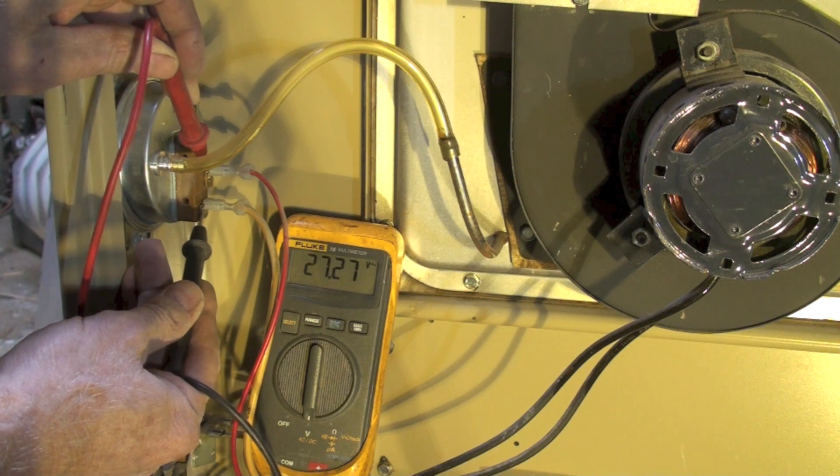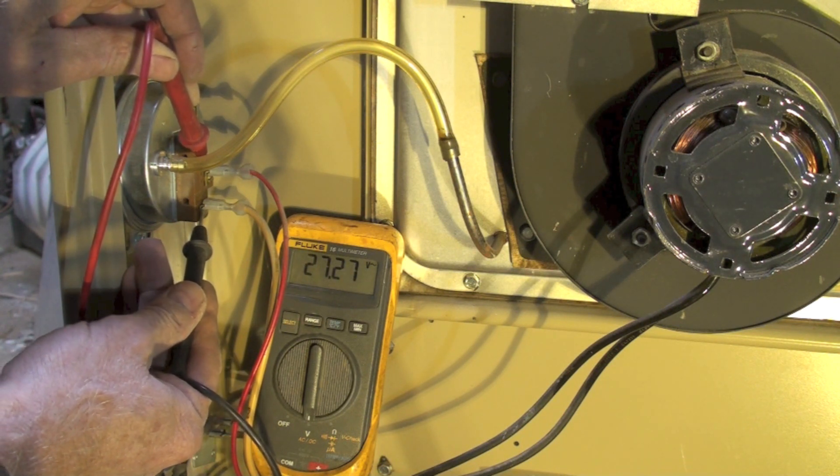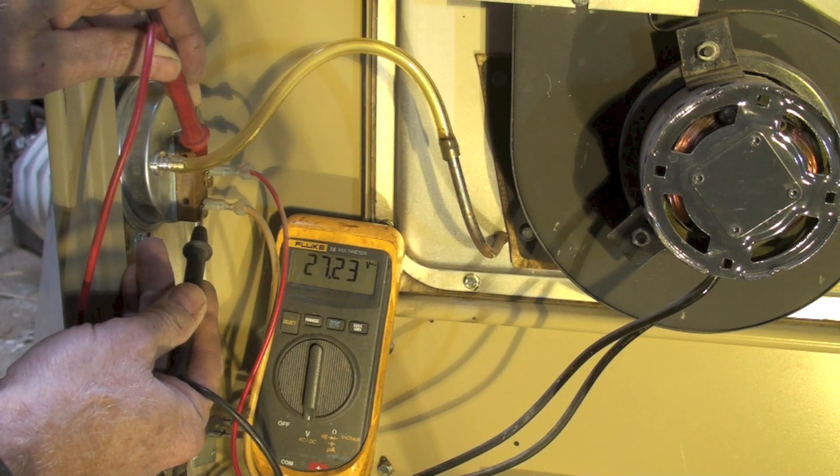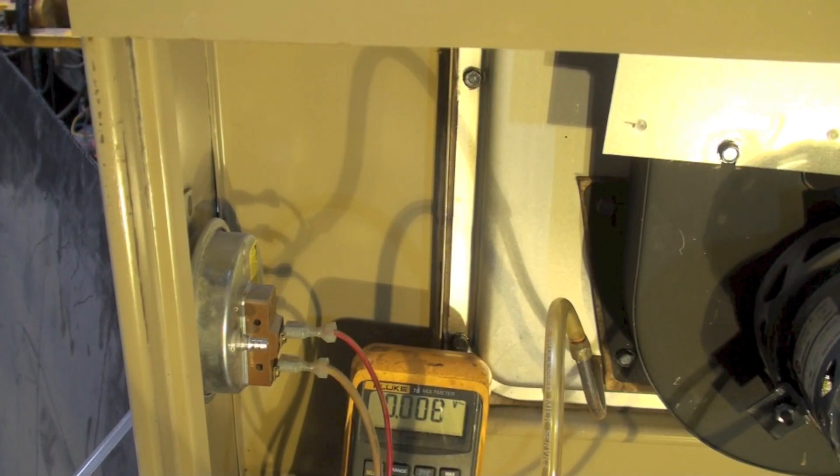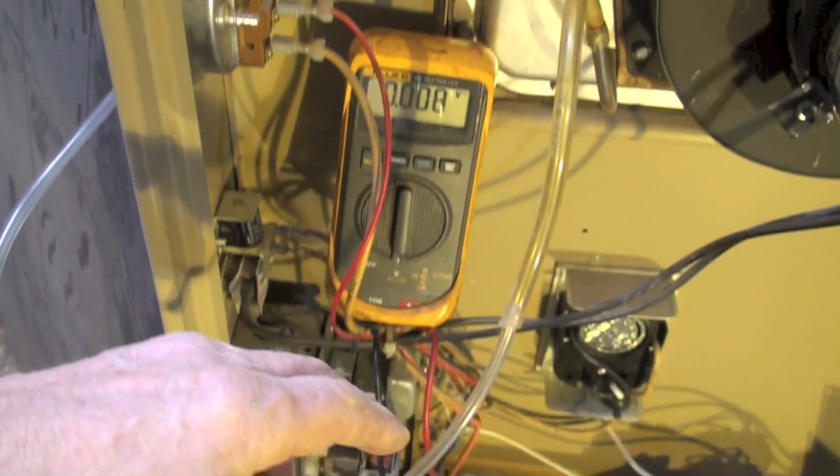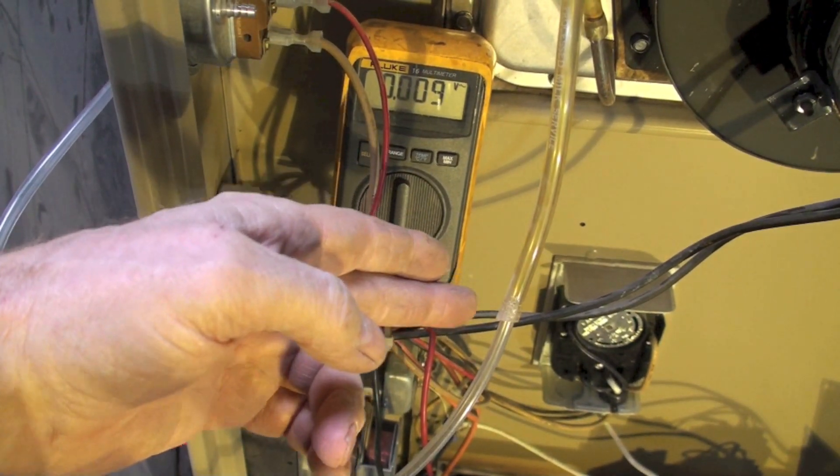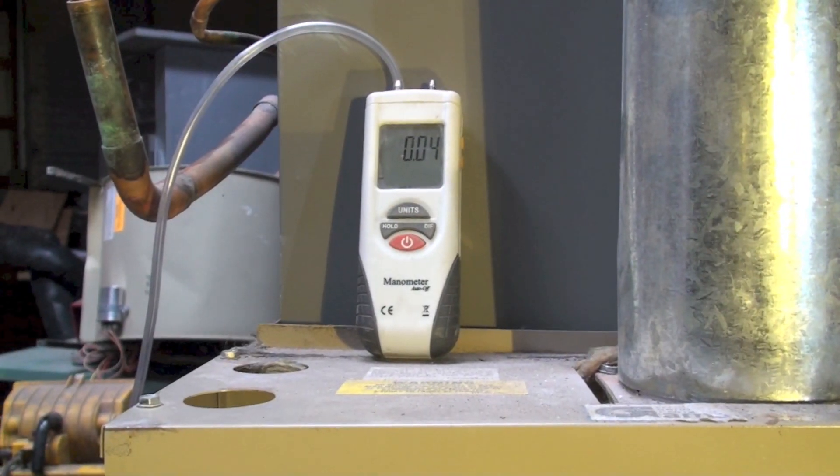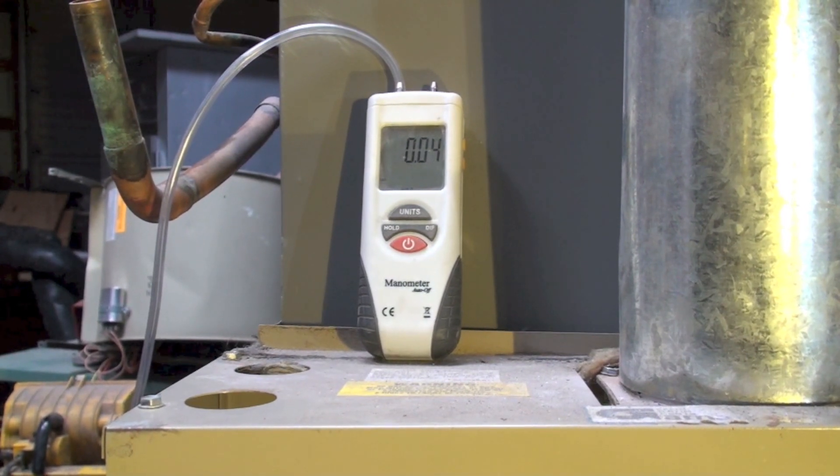Do I replace the pressure switch? Let's find out if we actually have any vacuum. What I've done is I've taken a manometer, hooked it onto this hose going to the inducer, and I'm showing virtually nothing.